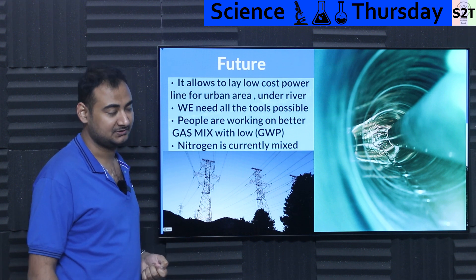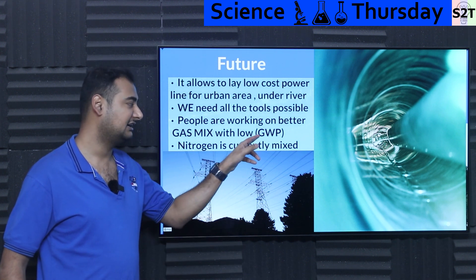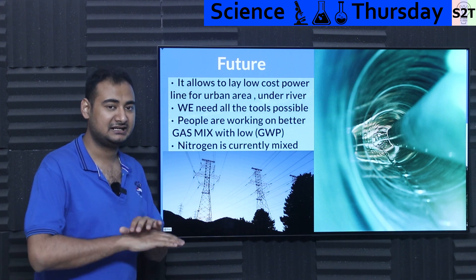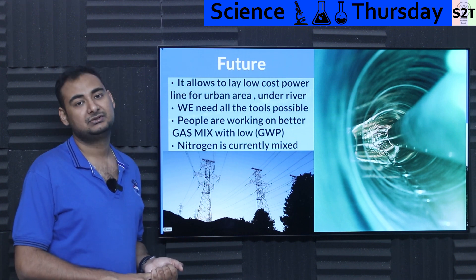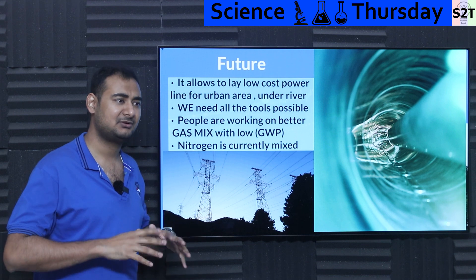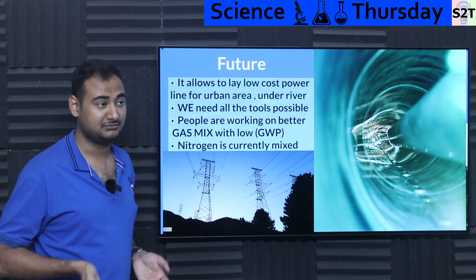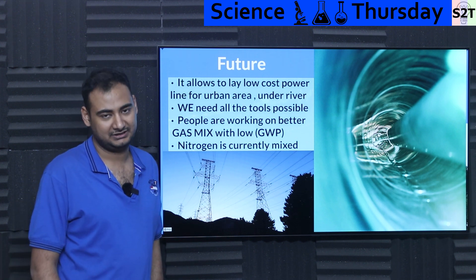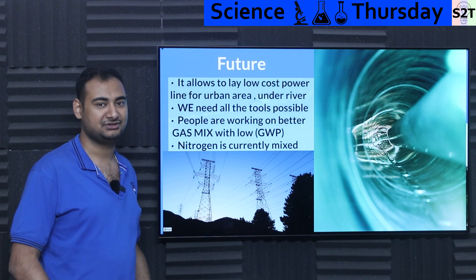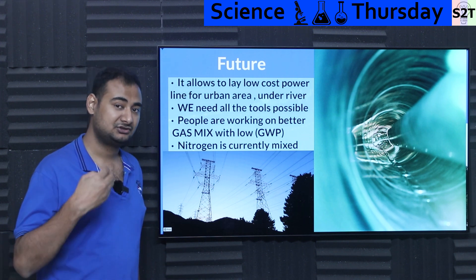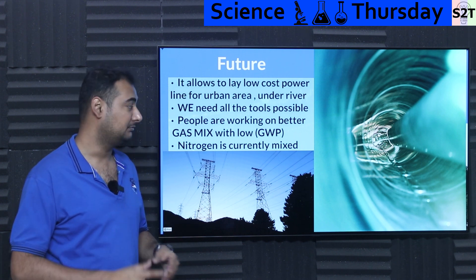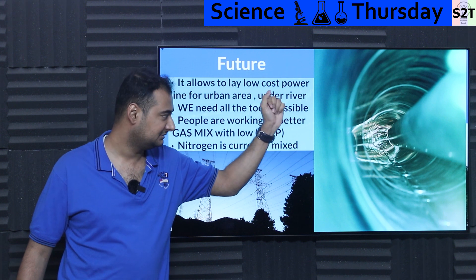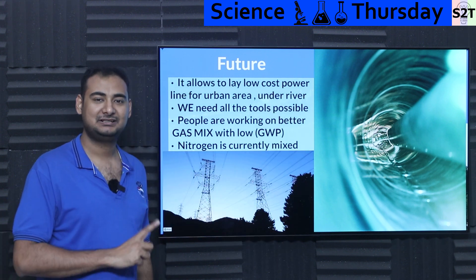People are working on better gas mixes because SF6 has a very high Global Warming Potential (GWP). Gen 1 technology used pure SF6; Gen 2 mixed SF6 with up to 80% nitrogen — nitrogen is an insulator but not as strong as SF6, though at lower voltages like 200 kV you can use nitrogen only, and since it's inert and already in the atmosphere, leaks don't matter. Companies are now working on Gen 3 technology using different synthetic gases with lower GWP and lower cost. This tube-inside-a-tube is our future — you may not see it yet, but it will be coming near you.